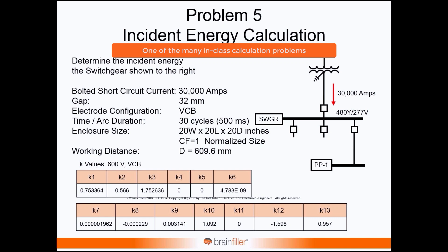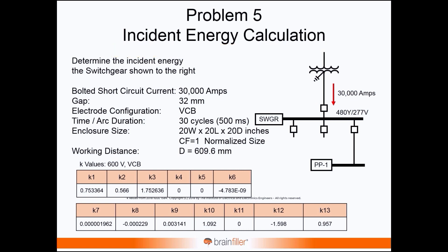In the 30,000 amp case I tried to make this identical to the case I had for my 2002 class. We had 30,000 amps of bolted short circuit current — 30kA. The gap used in the original problem was 32 millimeters because it's switchgear. The duration from the original 2002 class problem was 30 cycles, 500 milliseconds.